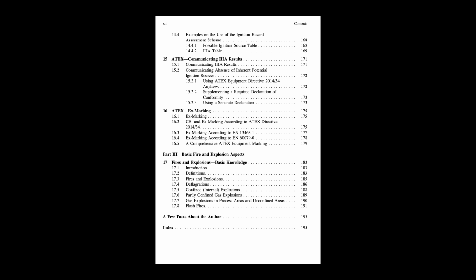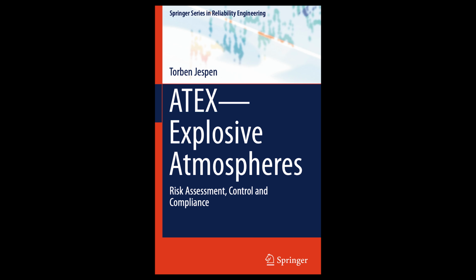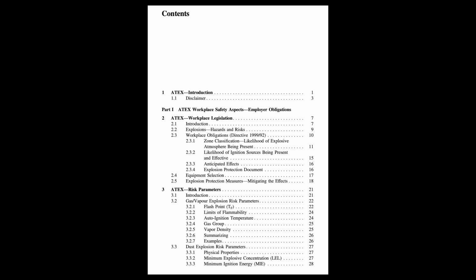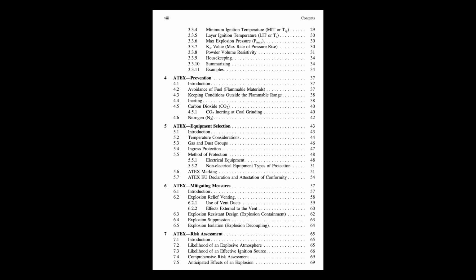What's number 3? Number 3 is explosion suppression. This is a more active system. Active? How so? It uses very fast-acting detectors, pressure sensors, or optical flame detectors to sense the very beginning of an explosion, like within milliseconds. Wow, that fast? Yeah, it has to be. As soon as it detects the initial pressure rise or flame, it triggers the rapid injection of an extinguishing agent, like a dry chemical powder, or even water mist directly into the vessel. So it snuffs out the explosion before it really gets going. Exactly. It stops the flame propagation and limits the pressure rise. It's like hitting the emergency brakes on the explosion itself.